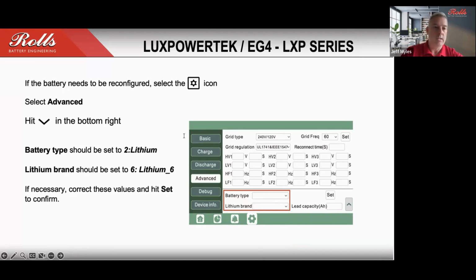It's going to explain to you which battery type to select from the menus. And we've worked with the inverter manufacturers to identify the best settings. They have also used our batteries in testing internally to verify that these settings are correct. So the guide that's provided, which is printed and included with the base and top assembly, will give you all of those settings as a walkthrough.